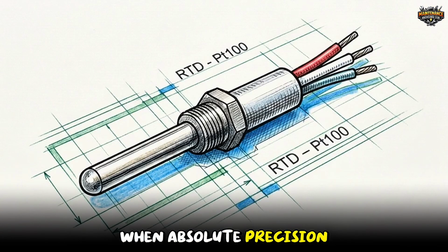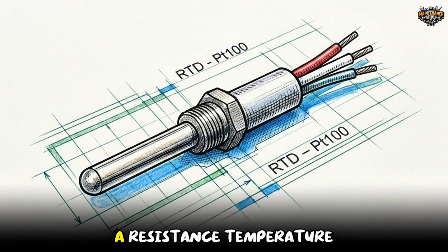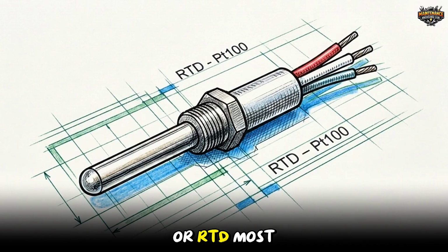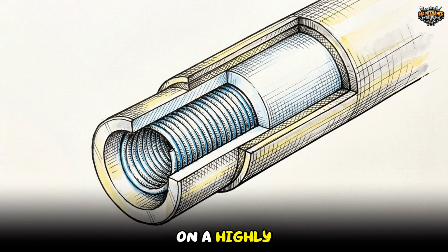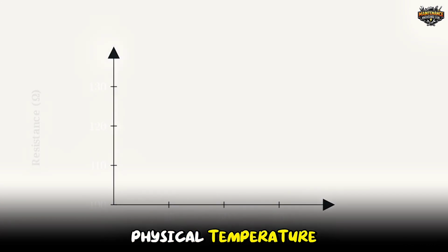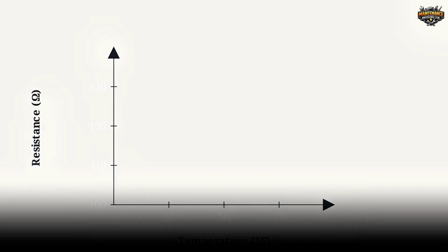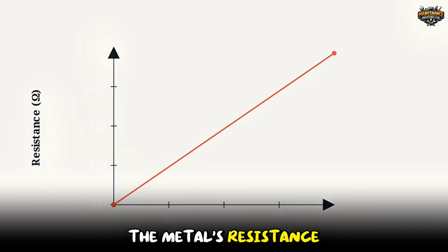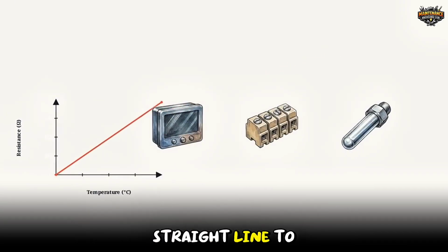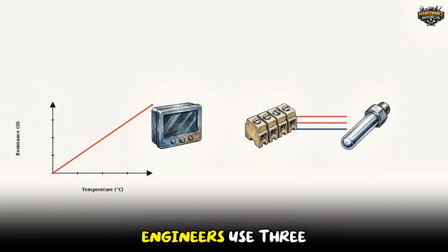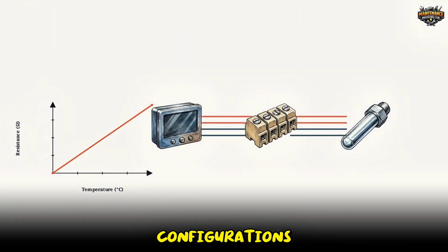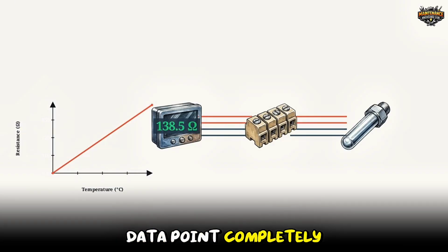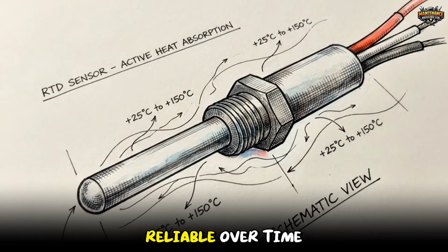When absolute precision is the goal, engineers reach for a resistance temperature detector, or RTD. Most of these rely on a highly stable metal, usually platinum, with the most common type being the PT100. This chart plots physical temperature against electrical resistance. As temperature rises, the metal's resistance increases in a steady, straight line. To ensure accuracy, engineers use 3- and 4-wire configurations to compensate for the cable's natural resistance, keeping the final data point completely stable. They are incredibly reliable over time.